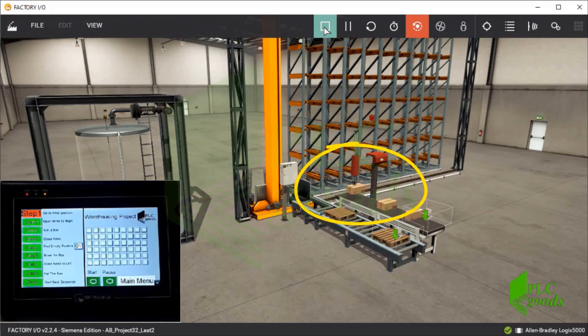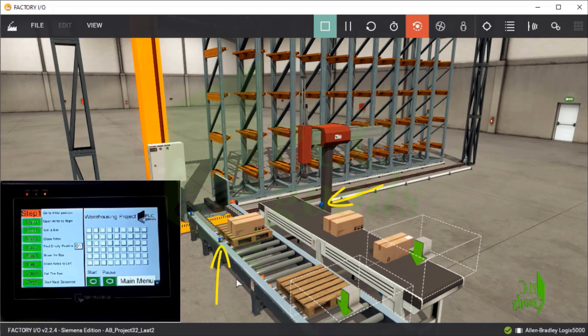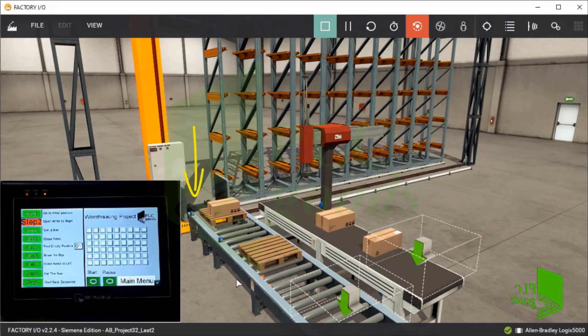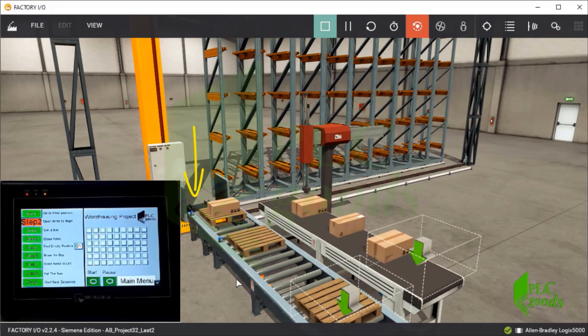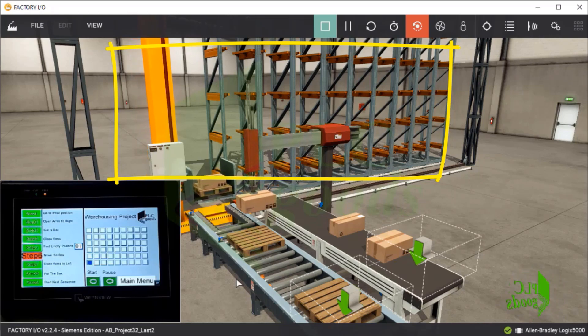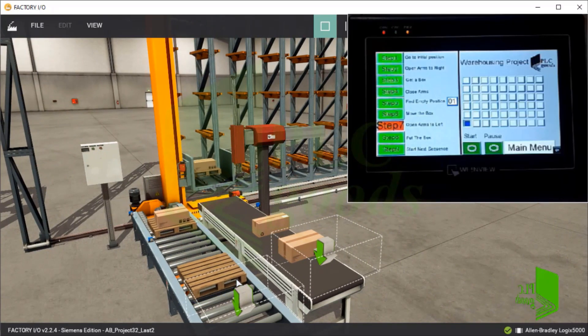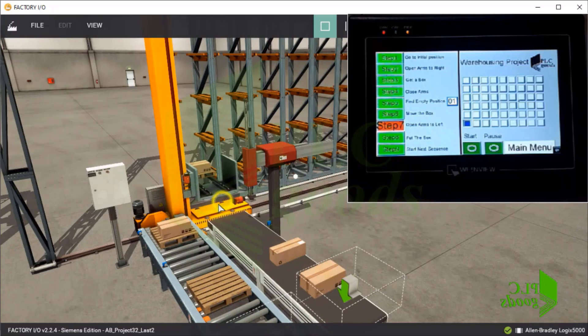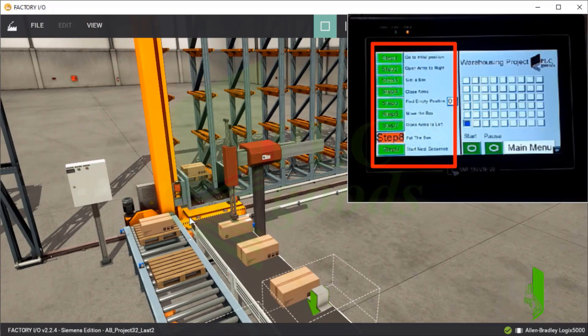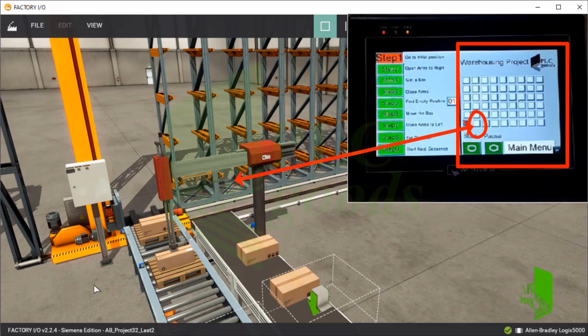As you can see, this arm picks up boxes and places them on pallets. There are two sensors used to detect boxes and pallets, and another sensor activates when a prepared box reaches the end of the roller — that's when the stacker crane starts its work. The stacker crane system and its program were explained during lessons 28 and 30. In lesson 30, we wrote an SFC program in 9 steps which placed boxes into empty positions automatically. I've used that with a little modification here. I've designed an HMI screen to display the stacker crane step, and on the right side, empty or filled positions are displayed. The second position inside the racks is currently empty, so the next box will be transferred there.